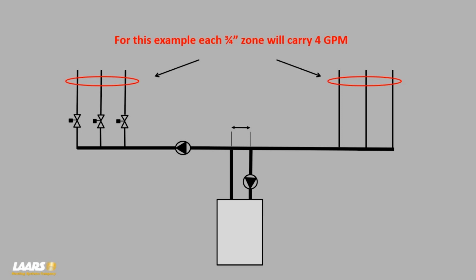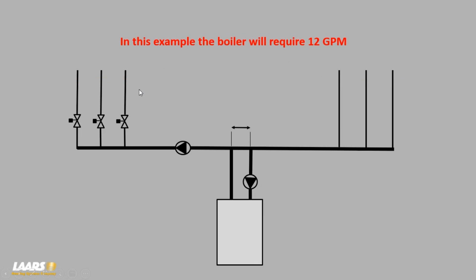Now, a 3/4-inch pipe can only carry 4 GPM. That's it. That's all you're going to get through a 3/4-inch pipe. Even if you put 2 pumps in series, what you're going to do is increase a head pressure, but you'll still only get 4 GPM. And that's important when I get to it. So I wanted to bring that up.